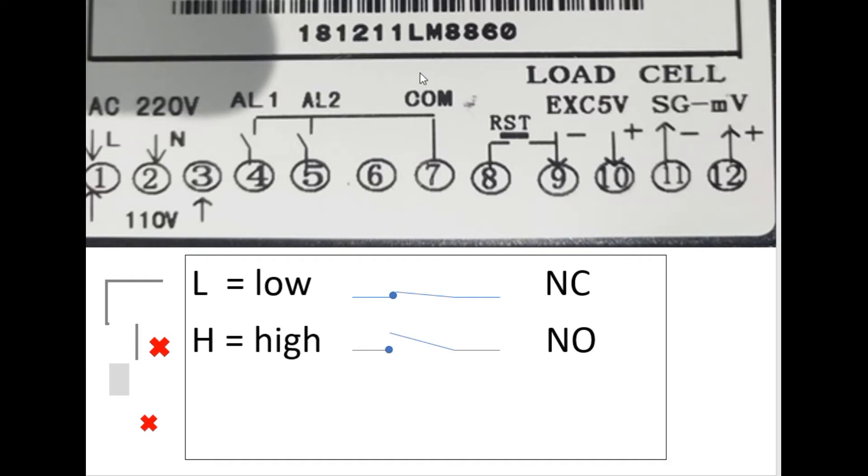Now the problem I'm facing here: number seven is the shared common for relay two and relay one. In my case, the machine will not work in this case, so I have to create another common for alarm one. For that, I have to open the load controller from inside, and let me just show you what I have done.